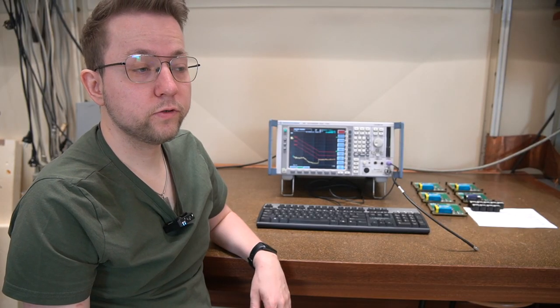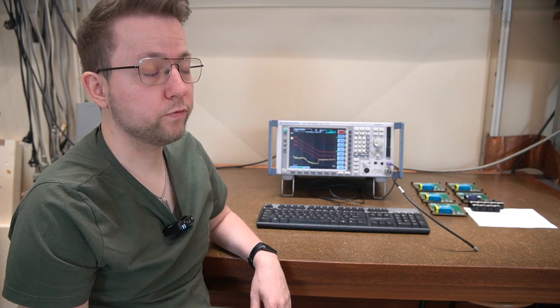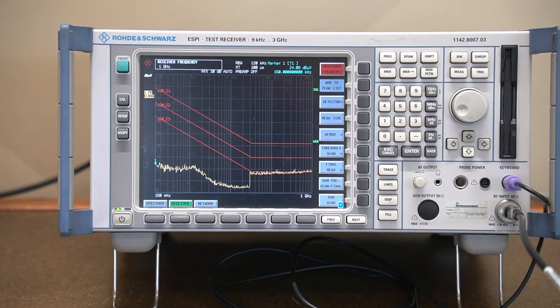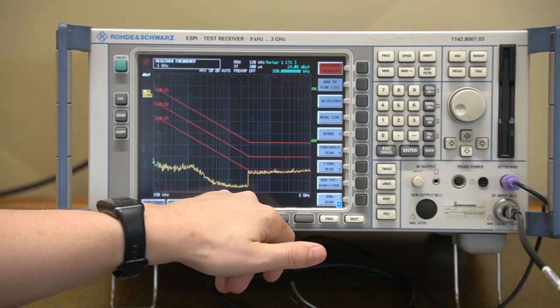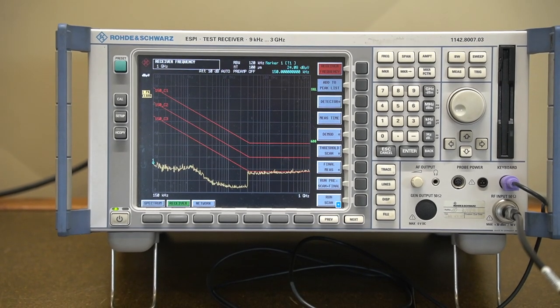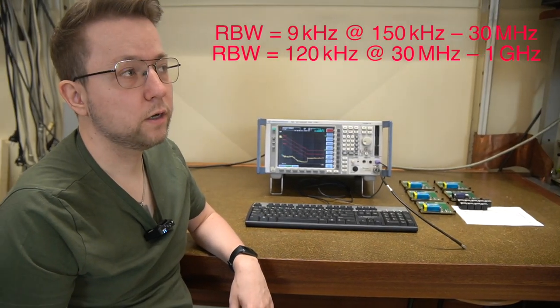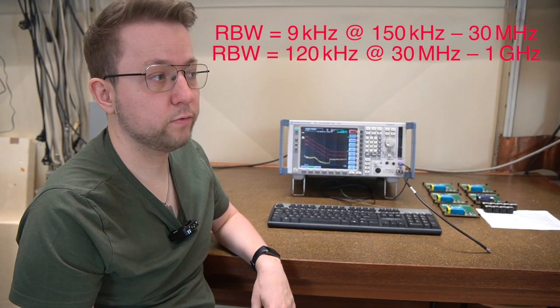So for our first measurement we basically measure the noise floor of the EMI receiver. This is done with our cable being not connected to anything. You can see here there is a drop for the range up until 30 megahertz. From there on it is switching into a different range where we have smaller or larger increments so the measurement doesn't take forever.